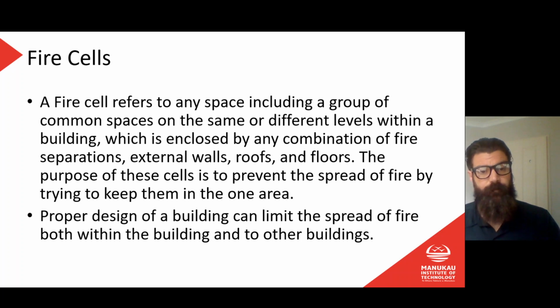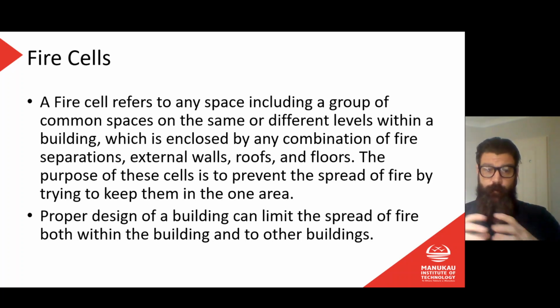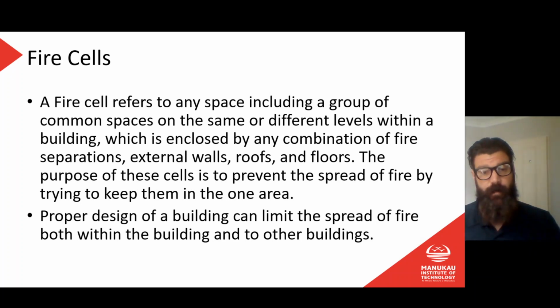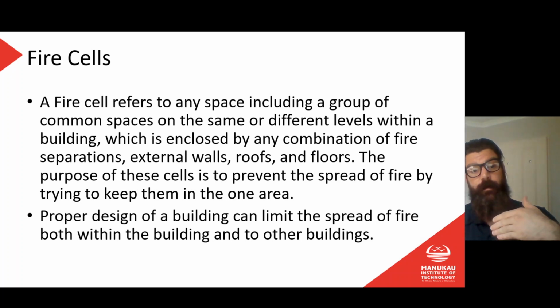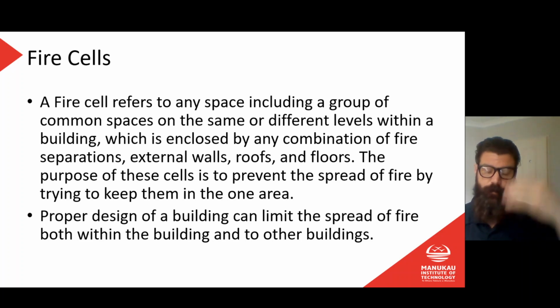But any services that come up between floors will generally be all together. So you'll probably find there'll be a service cupboard somewhere, and that will have access up and down, and then that cupboard itself will be enclosed by further fire separations. So if there's a fire on one level, it's not going to penetrate into that service cupboard and then upwards to the next floor. So there'll be a fire separation around what you'd call the service cupboard or service shaft going from top to bottom. You'll also find that the stairwells would be enclosed by fire separations, so that no fire in any floor is going to spread into the stairwell, because that would potentially affect the evacuation of people on the floors above.